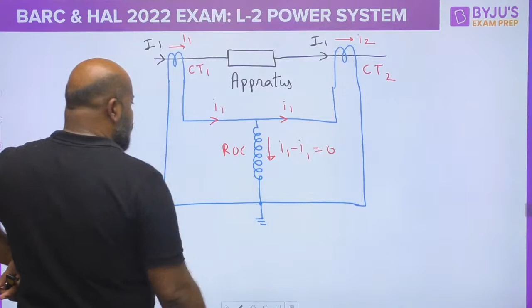Because of the current transformer, this is CT1, because of some turns ratio, some transformation ratio, this current will be coming something like this, a small I1, and for current transformer 2, some current must be coming like this, I2. So the current which is passing through the relay operating coil is going to be I1 minus I2, which is equal to 0. So there is zero current passing through the relay operating coil. There is no way that the relay can operate and send a trip signal to the circuit breaker. And that should be the case because it is a healthy system.